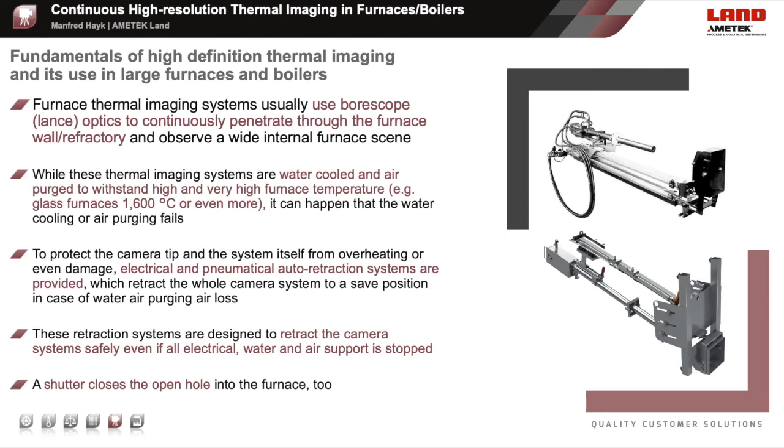Furnace and boiler monitoring systems are typically designed with borescope or lance optics. The tip of the boroscope optic is exposed continuously to the hot and dusty furnace atmosphere. With the water cooling and air purging, they can even withstand furnace temperatures higher than 1600 degrees Celsius. To protect the camera tip and the system itself from overheating or damage, it will be retracted to a safe position in case of water, air purging, or power loss. An additional mechanical shutter separates the furnace atmosphere in front of the camera opening from the outside. These are very safe systems working reliably in many furnace and boiler applications globally. Auto-retraction systems are an option available for nearly each furnace camera system.